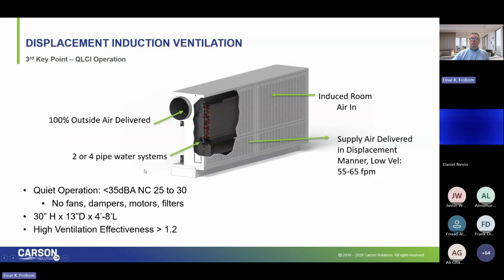So how does the QLCI work? The QLCI is a chilled beam. It is an induction unit. Use your favorite terminology. But the heart of the operation is the fresh air that's coming to the diffuser from the DOAS unit. And the typical dimensions of this diffuser is 13 inches in depth, 30 inches in height, and anywhere between 4 feet on up to 8 feet in length. And typically in a classroom, you would have 3 of these diffusers directly connected. They don't have to be directly connected, but typically they are in some fashion.